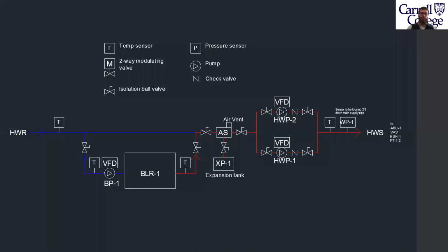I've also included a flow diagram to explain the primary-secondary loop. The boiler is on a separate loop so that not all the hot water has to run through the boiler. It can bypass the boiler if it doesn't need to be heated very much. You can also see the two pumps for the circulating system. In case one of the hot water pumps fails, the other one can run instead. And then the isolation valves can be closed and the pump can be removed for replacement or repair.